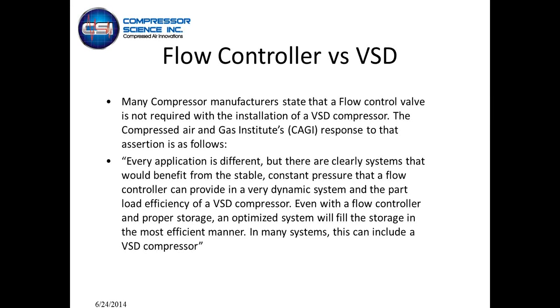So segregating supply from demand, to me, is very important, because you're allowing the compressors time to deal with events in the plant through storage and control, including VFD. The VFD will trim at the bottom end to make sure the receiver tank has enough volume when the flow controller is opening, to maintain that volume out in the system at a steady pressure. Providing there is sufficient storage, it'll work properly.